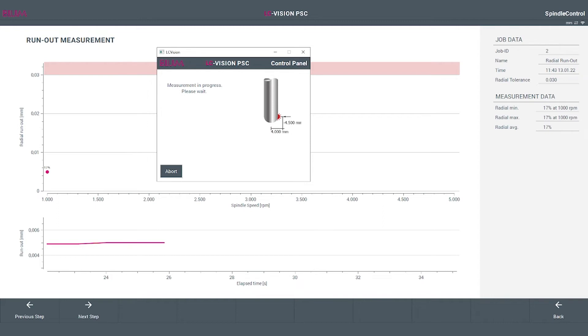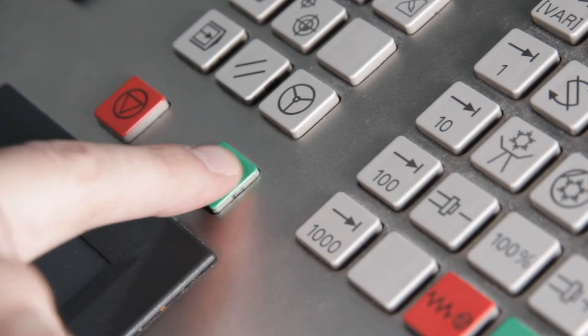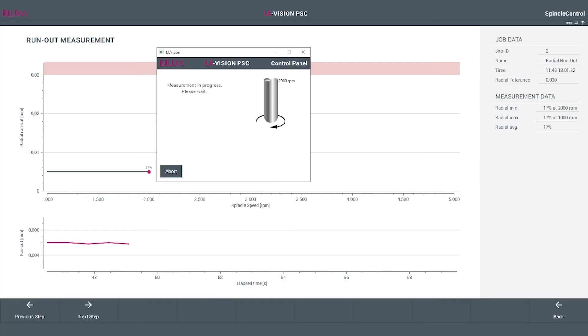In addition, the LC-Vision PSC continues providing guidance on performing measurements and analyses until the job is done. For example, you will be asked to enter speeds on the control as you had defined them initially when creating the job. You can also track the measurement progress and values live on the screen. Thus, you always have everything in view and can immediately make statements on the condition of your spindle.